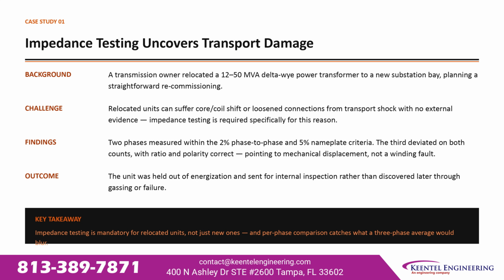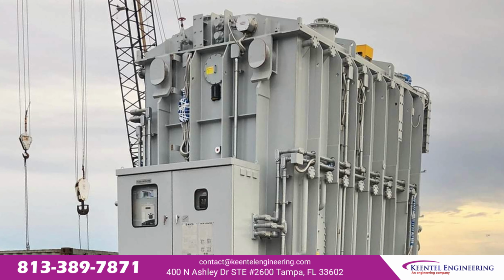2 phases measured within the 2% phase-to-phase and 5% nameplate criteria. The third deviated on both counts, with ratio and polarity correct, pointing to mechanical displacement, not a winding fault. The unit was held out of energization and sent for internal inspection, rather than discovered later through gassing or outright failure. The takeaway: impedance testing is mandatory for relocated units, not just new ones, and per-phase comparison catches what a 3-phase average would blur.